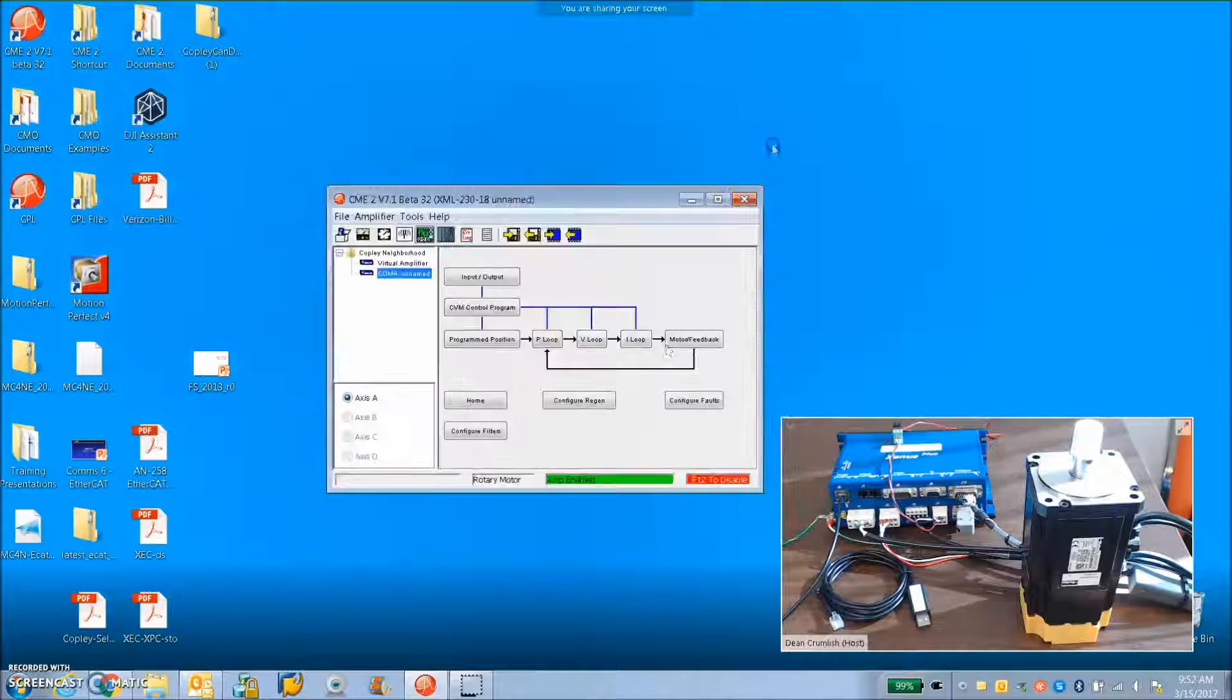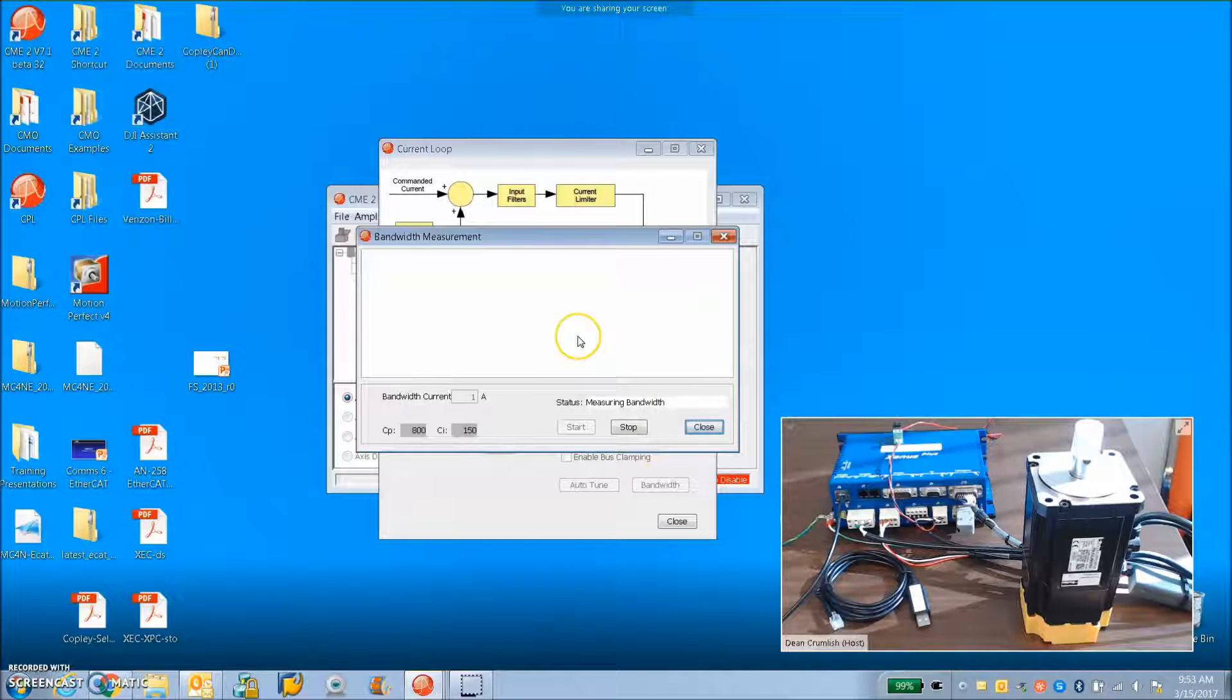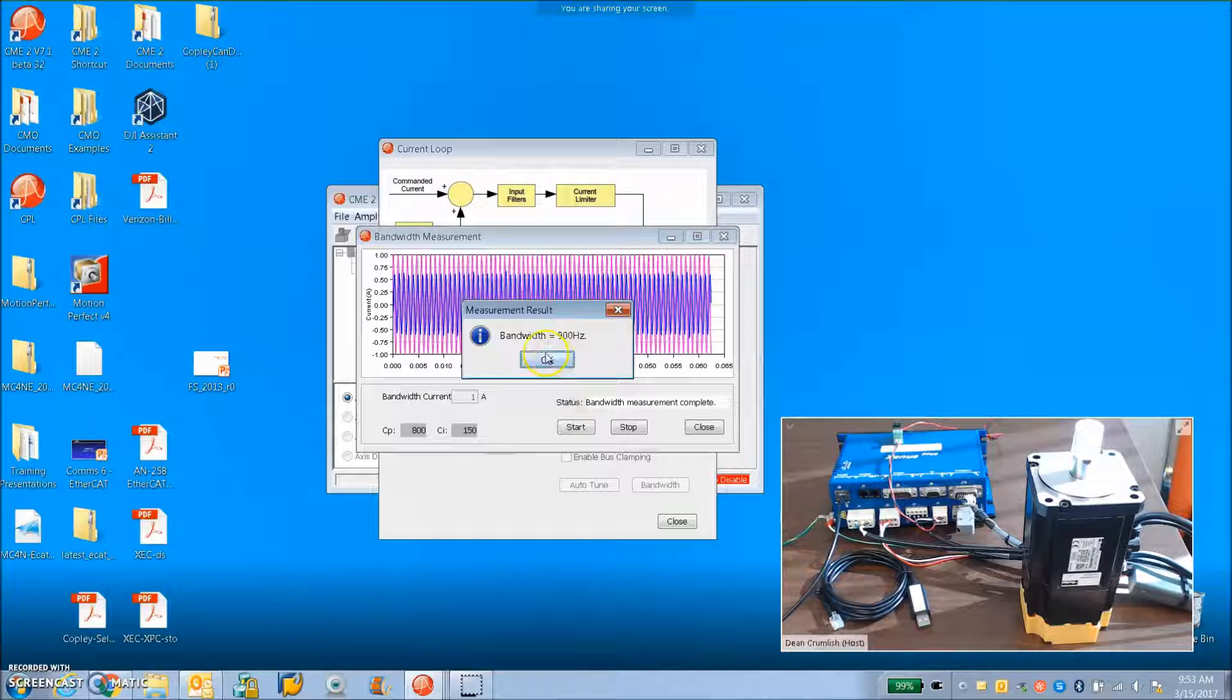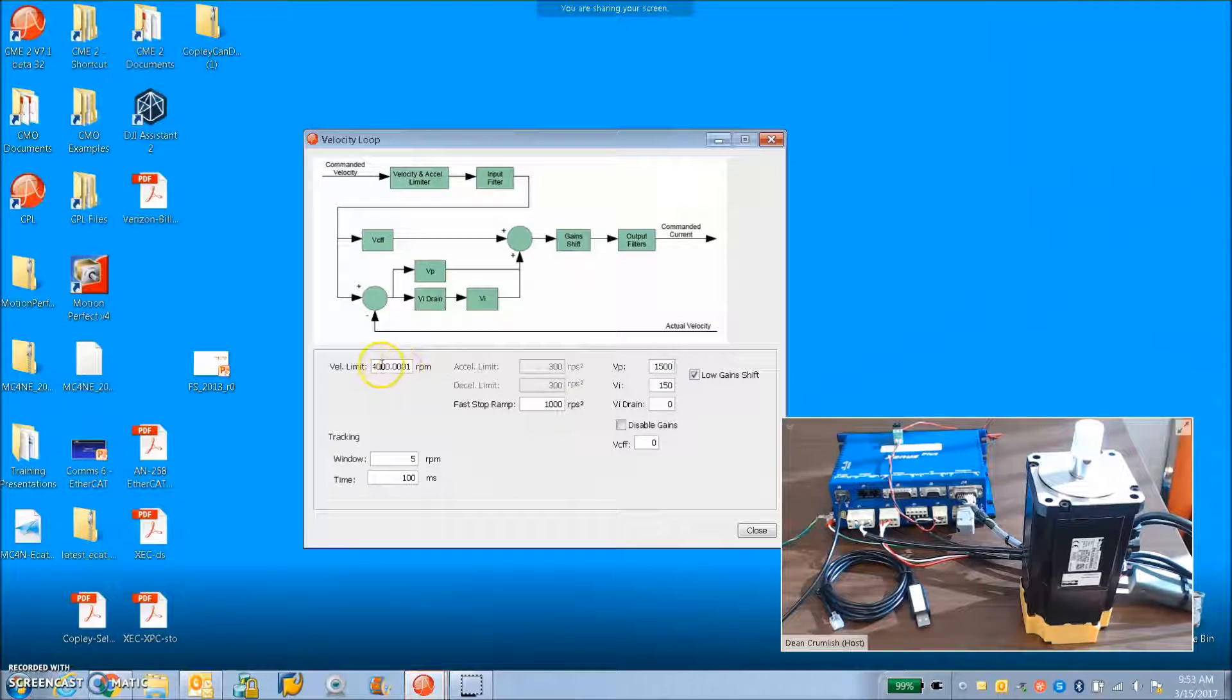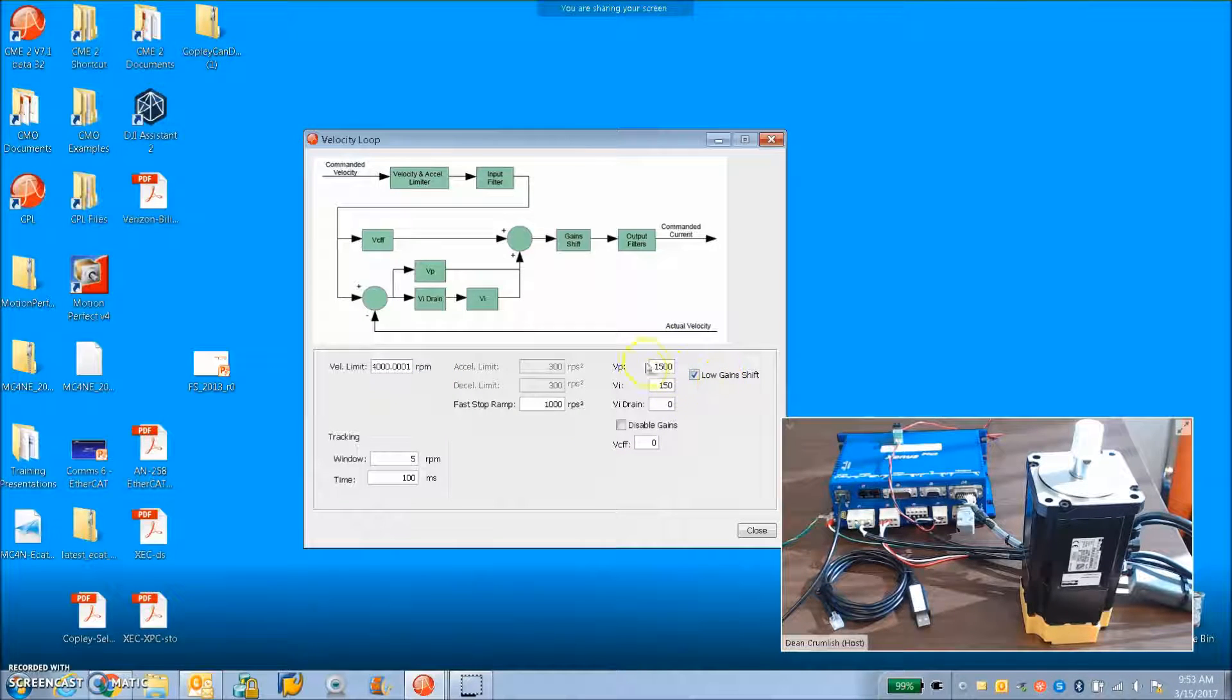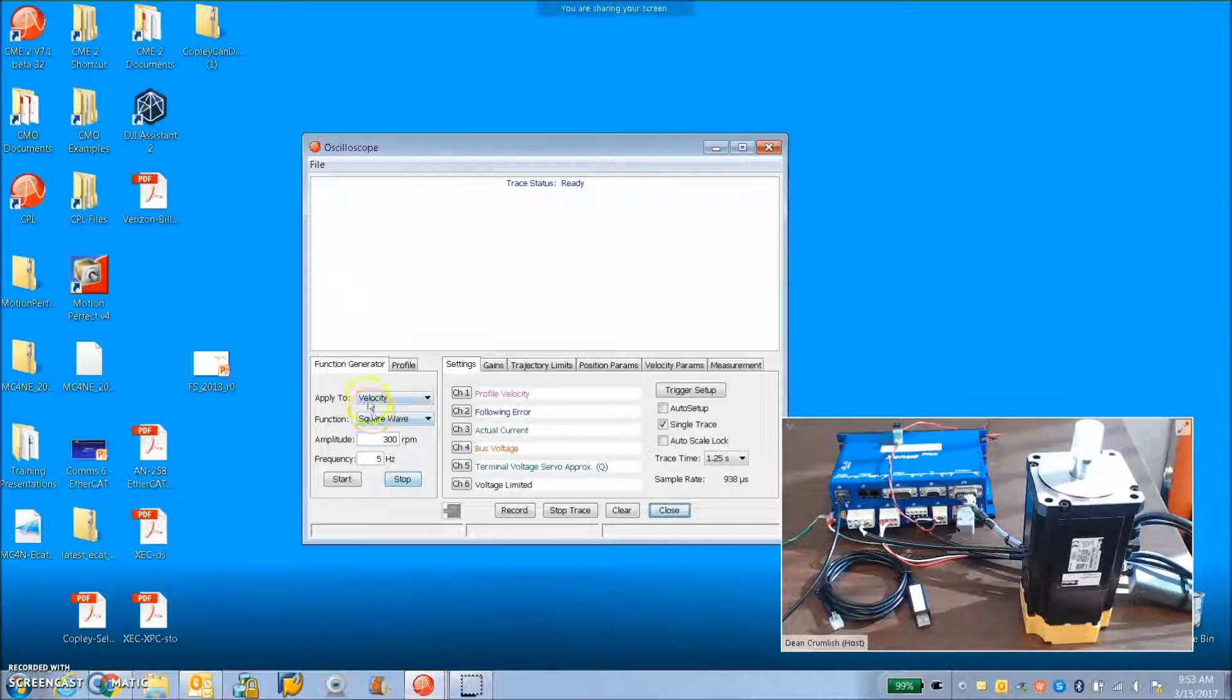I'm going to go real quick through the settings here. We've got peak and continuous current. This is the amps peak, so RMS would be more than that. The gains of the current loop were tuned. I should get about a kilohertz of current loop bandwidth. Maybe 800 hertz is fine. There's a little bit of inductance in this motor, about 4 millihenries, so we don't want crazy bandwidth on this. I set the max speed limit to 6,000, so my velocity limit will come up at 3,000. But this motor on 120 volts AC can go a little faster, so I set the limit up to 4,000. I've got my gains adjusted so it doesn't oscillate. I haven't messed with the P-loop gains. Those are the calculated values. But I'm going to run through the tuning real quick here.